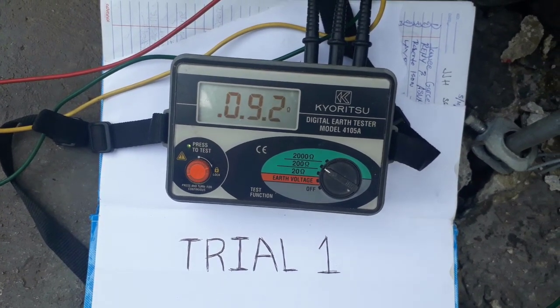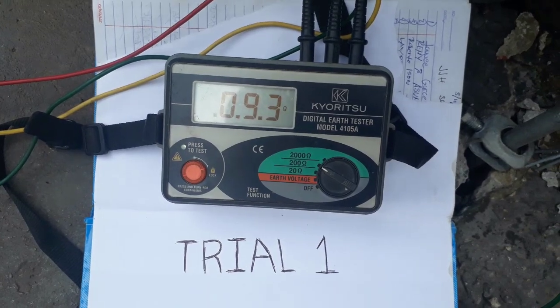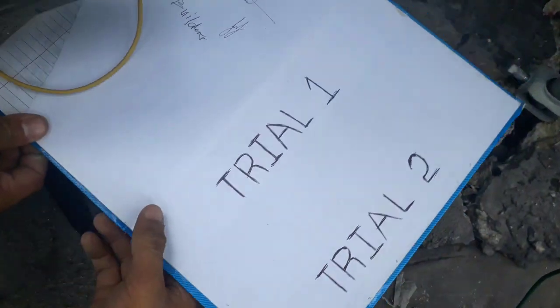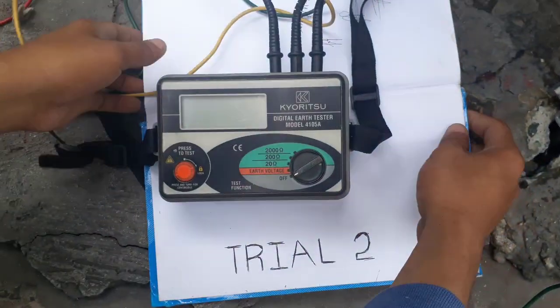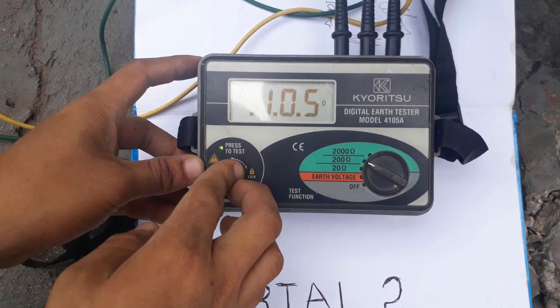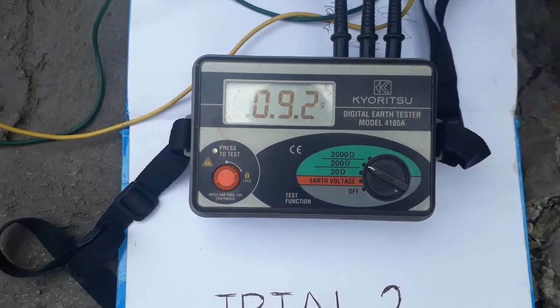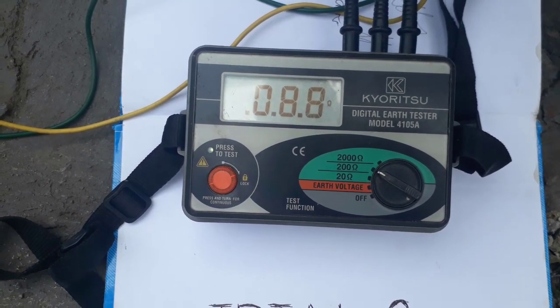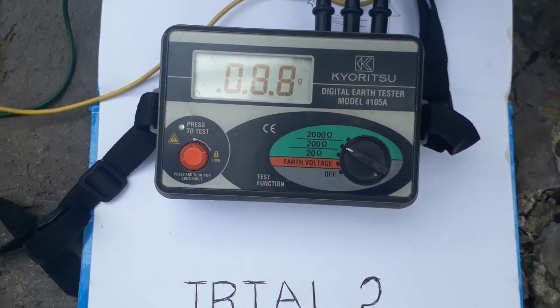One factor that affects the resistance value is the existing soil condition. Conduct another test by moving the test rod's position to another location. Run the same test and note the value of the resistance. Mark the second test as the second trial. As you may see, the value of the resistance changed to 0.88 ohms after the test.